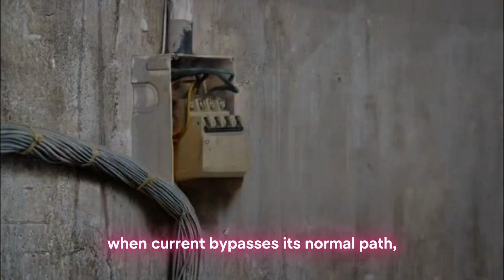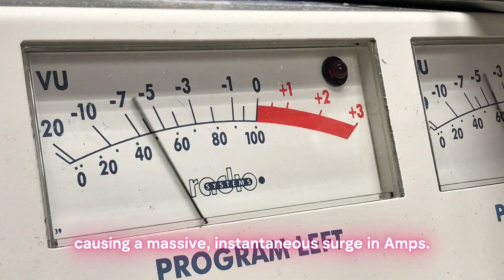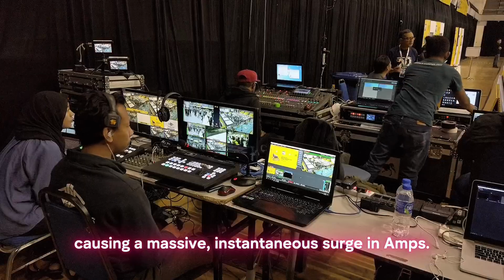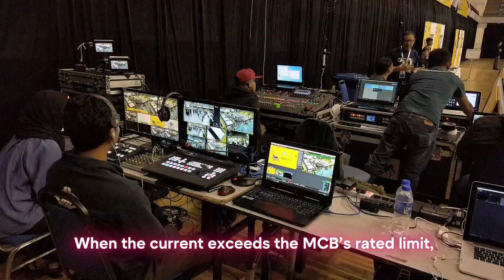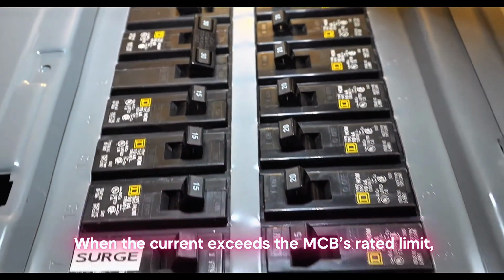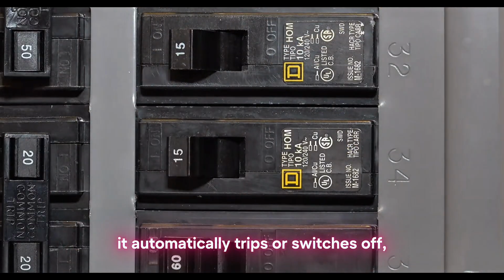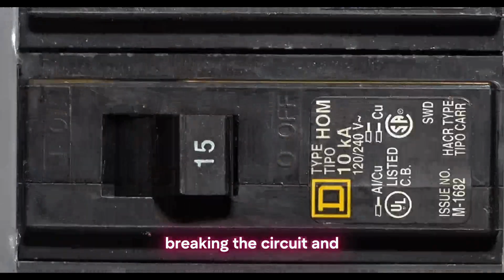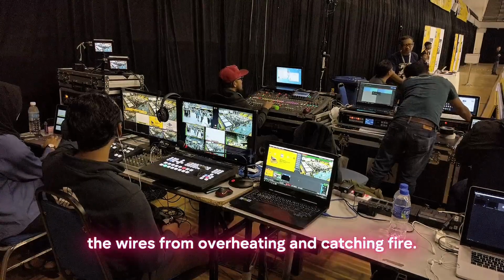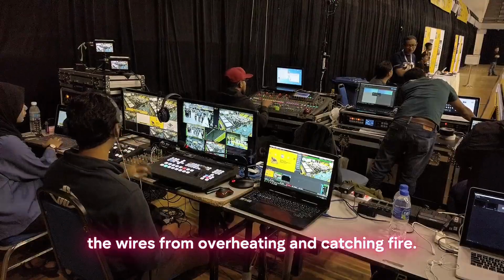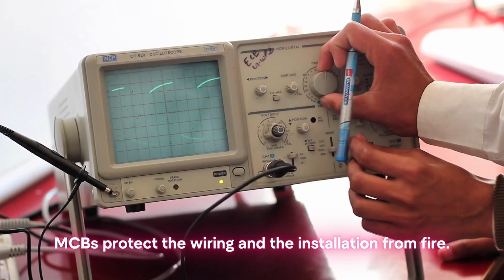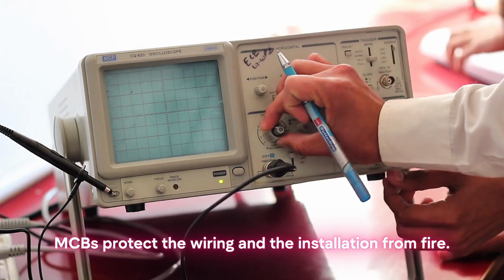And number two, short circuits, when current bypasses its normal path, causing a massive, instantaneous surge in amps. How it works? When the current exceeds the MCB's rated limit, it automatically trips or switches off, breaking the circuit and stopping the flow of electricity to prevent the wires from overheating and catching fire. MCBs protect the wiring and the installation from fire.